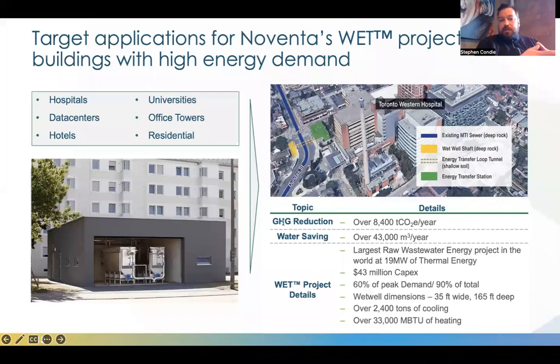In this application, and since this is what we're all talking about, is greenhouse gas reductions, in our first phase, we're looking at reducing the hospital's carbon footprint by 8,400 tons a year. As well, because we're providing that cooling aspect and we're able to offset cooling towers by using wastewater and rejecting heat back to the sewer, we're offsetting over 43,000 cubic meters of water, which I believe was roughly around 19 Olympic-sized swimming pools each year.